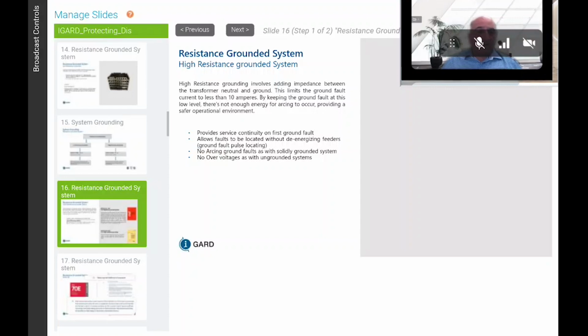So we go with high resistance ground in the system. So it provides service continuity on the first ground fault. When you get a ground fault, you basically convert your high resistance grounded system to a solidly grounded system. You've limited the fault current to less than 10 amps, so you don't have an arc flash trigger. And there are no overvoltages associated with the ungrounded system as long as you choose the resistor so the resistive current is equal to or greater than the capacitive charging current.